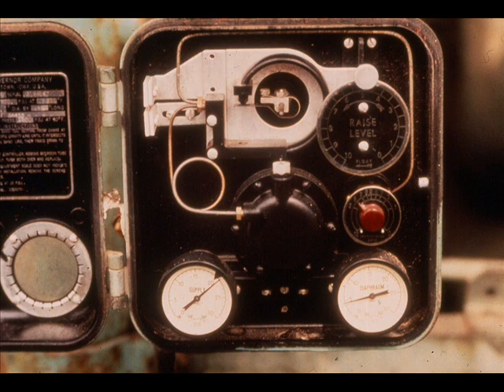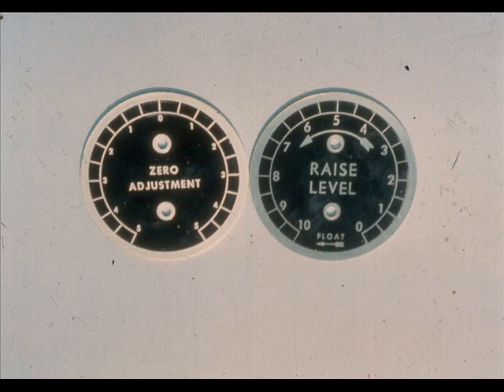Perhaps your plant uses the Fisher 2500 LevelTrol. It is designed to control, but it is commonly used as a transmitter. It is built and works just like the 2500T, but the zero adjustment is called 'raise level.' It does the same thing as the zero adjustment on the transmitter.